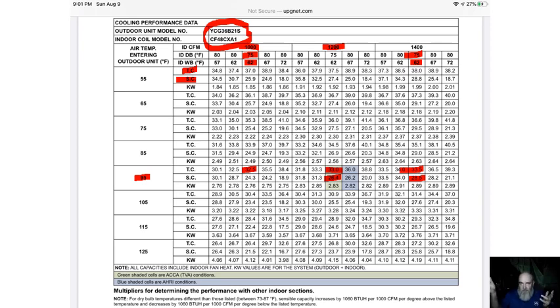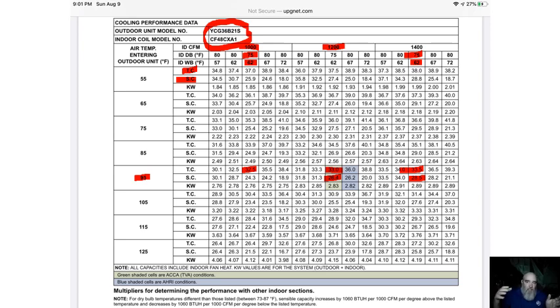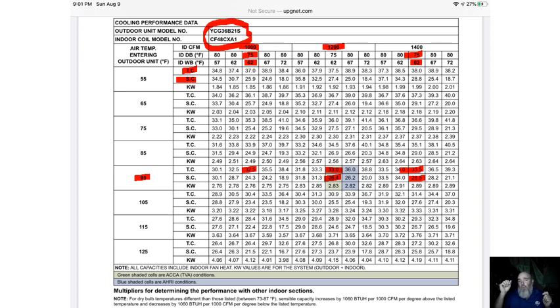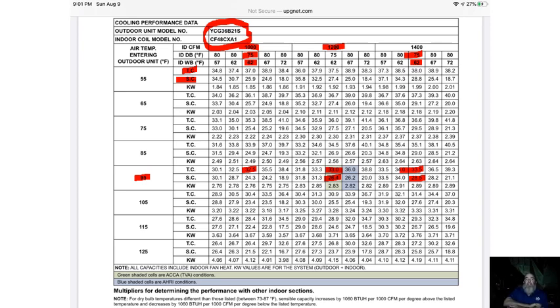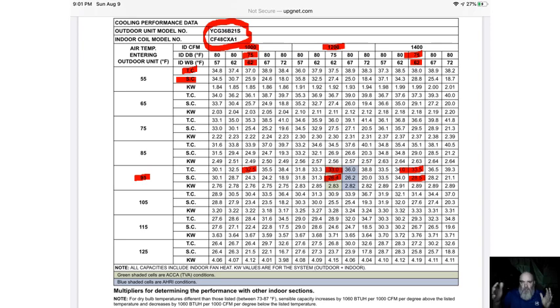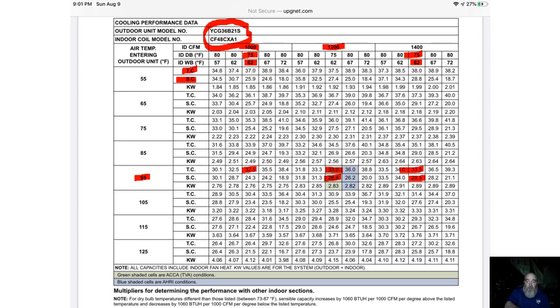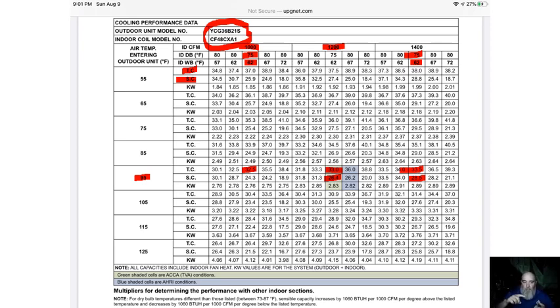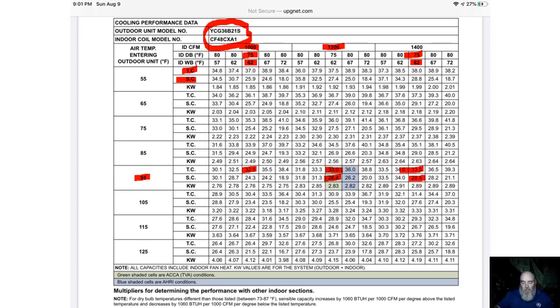That's how an air conditioner works. More air across the evaporator coil, the higher your sensible heat ratio. The slower the air, the lower the sensible heat ratio. You can't say a specific piece of equipment or combo of equipment will do something just solely based off of your coil choice, because it's not true. This chart shows it. If you want to start talking about what happens with a piece of equipment, you have to include the indoor and outdoor section, and in addition to that, how much air is moving across the coil, because it all plays a part in how an air conditioner functions.